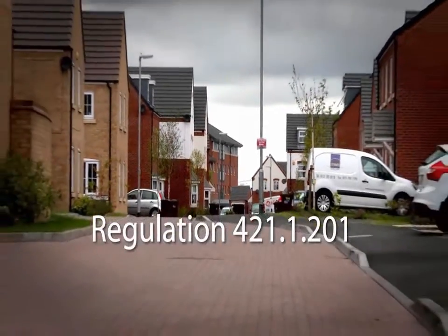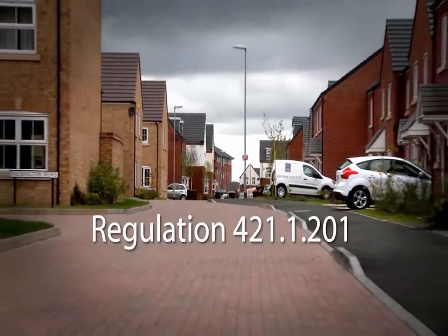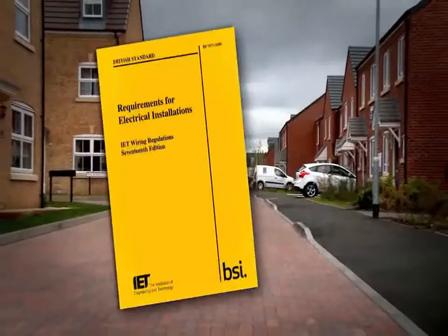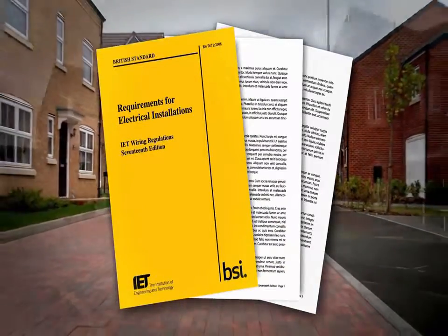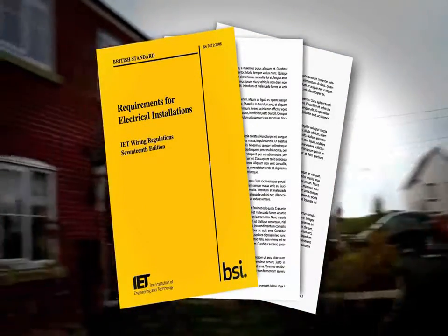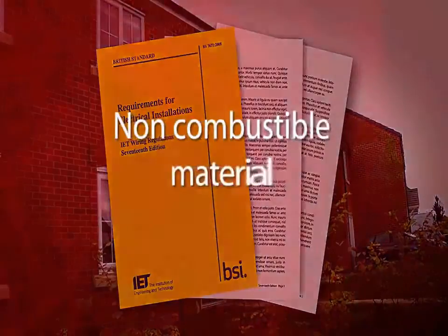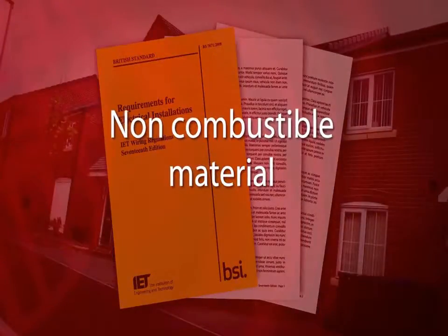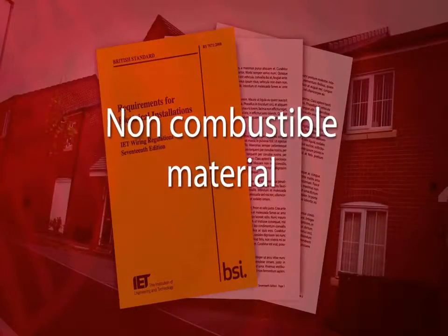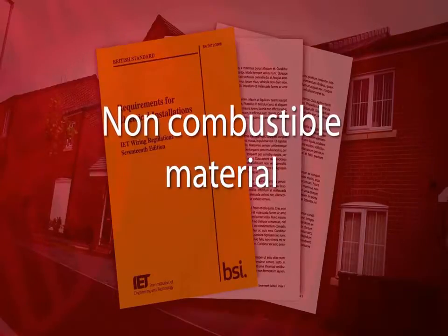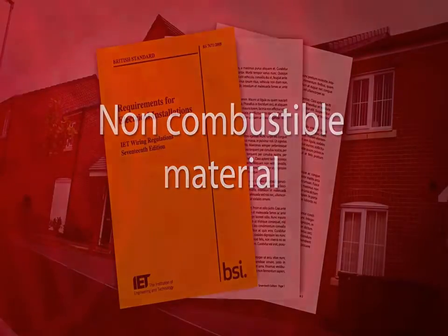Regulation 421.1.201 in Amendment 3 of the IET wiring regulations requires consumer units for use in domestic household premises to have their enclosures manufactured from non-combustible material. The intent of Regulation 421.1.201 is to contain any fire that may occur within the consumer unit.